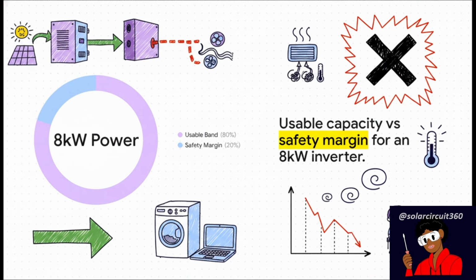Let's totally bust a myth right now regarding an 8-kilowatt inverter. An 8-kilowatt inverter does not, I repeat, does not give you 8 kilowatts of usable, continuous power. It just doesn't. If you try to pull a continuous 8-kilowatt load on that hardware, it will fail. We always have to apply a safety margin, which usually means keeping our continuous load right under 80% of the maximum rating. So your practical, usable load band is really only about 6.4 kilowatts.